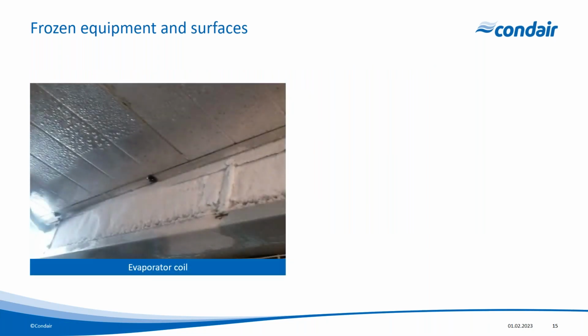And then, of course, we've got equipment surfaces. So it takes a little bit of an explanation for this photograph. For those of you that are familiar with cold stores, you will know this is the rear of an evaporator. So we've got the fans on the opposite side of the evaporator. This is a ceiling mounted evaporator where the air is coming over this coil.